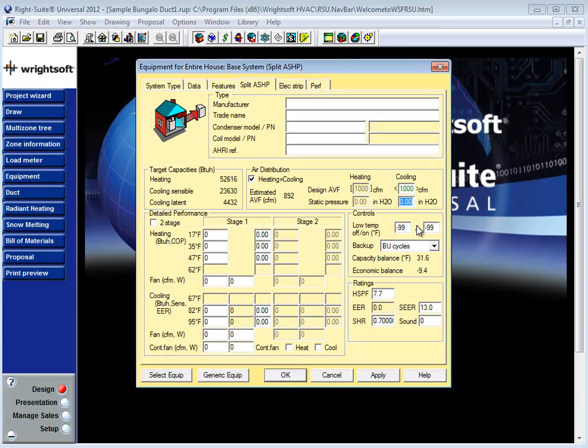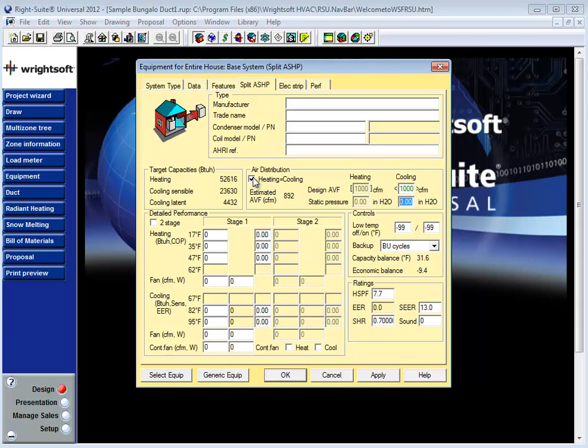Now speaking of those CFM we do have one other option here that we can exercise. The default setting in Wrightsoft is to use a heating equals cooling design meaning that your heating CFM will be based on your cooling CFM. Your heating static pressure will be based on your cooling static pressure. This is a common design tactic in a situation where your heating and cooling CFM may be variable but your ability to seasonally balance a duct system is significantly hampered. Using a heating equals cooling design will ensure proportional design for any individual duct runs that might call for more heating or cooling CFM.